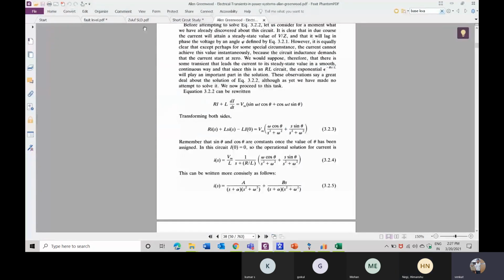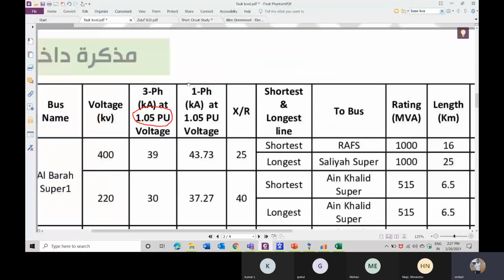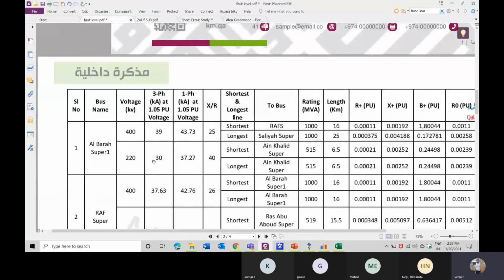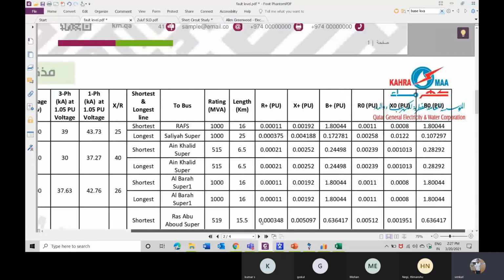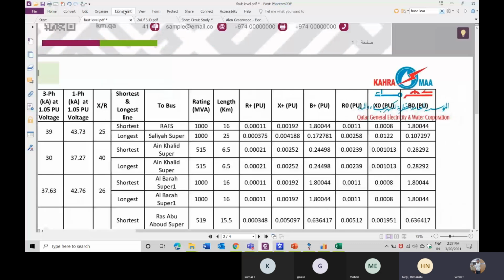That part I will show you. Here you can see this fault level document — you have to take it as an input from the customer itself. Here you can see there is something called zero sequence per unit, X naught per unit, resistance, reactance, and for susceptance or capacitance, they have given all of it.